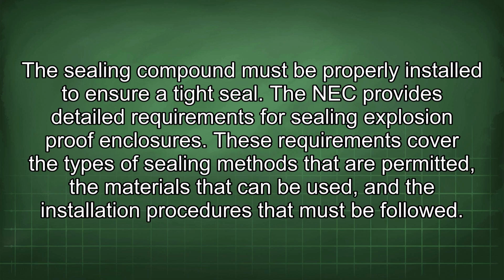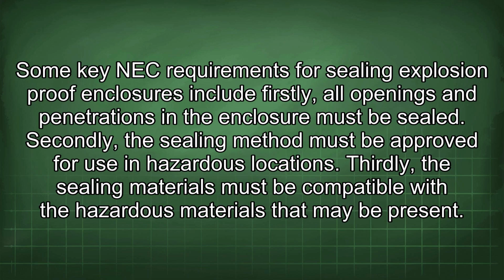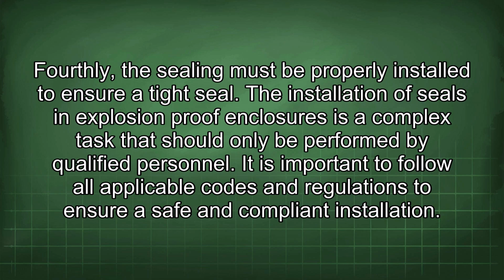The NEC provides detailed requirements for sealing explosion-proof enclosures. These requirements cover the types of sealing methods that are permitted, the materials that can be used, and the installation procedures that must be followed. Some key NEC requirements for sealing explosion-proof enclosures include: firstly, all openings and penetrations in the enclosure must be sealed. Secondly, the sealing method must be approved for use in hazardous locations. Thirdly, the sealing materials must be compatible with the hazardous materials that may be present. Fourthly, the sealing must be properly installed to ensure a tight seal. The installation of seals in explosion-proof enclosures is a complex task that should only be performed by qualified personnel. It is important to follow all applicable codes and regulations to ensure a safe and compliant installation.